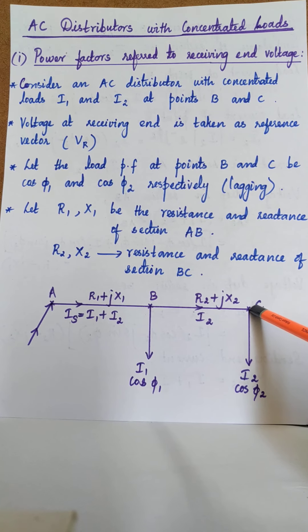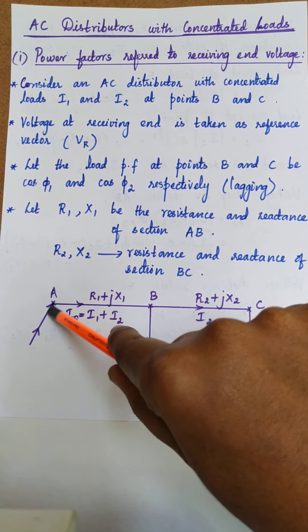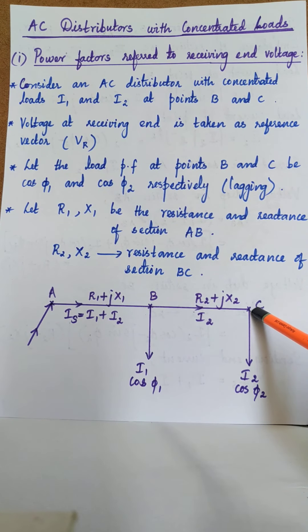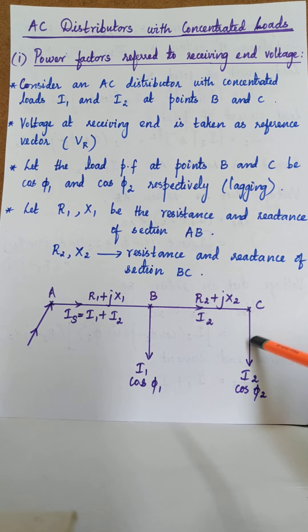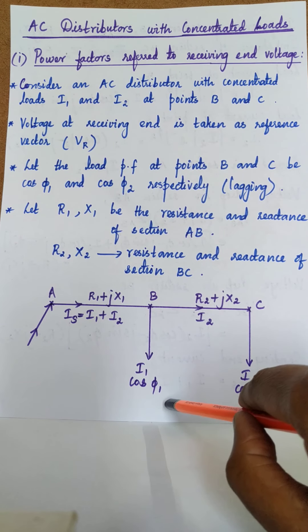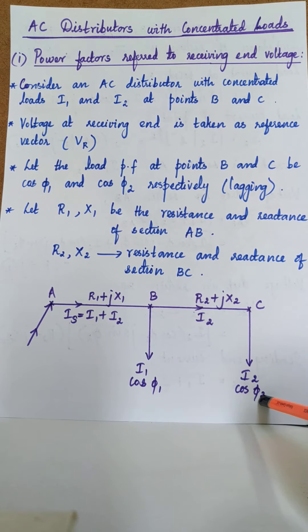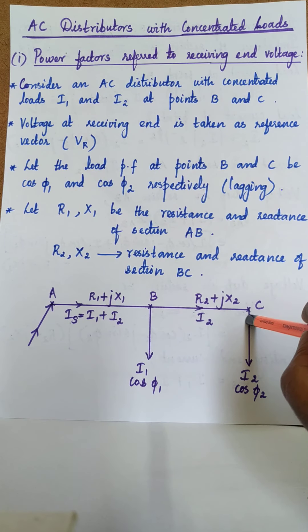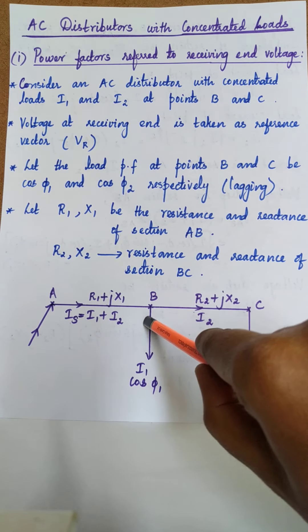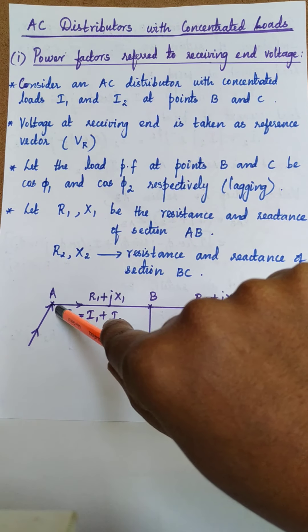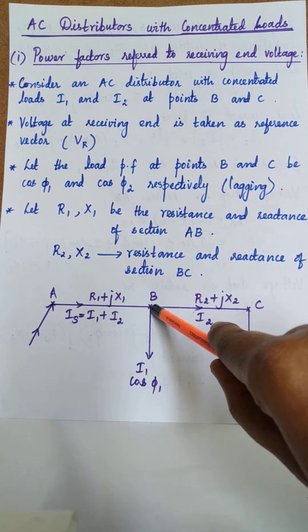The receiving end side is point C, and the sending end side is point A. The receiving end voltage at point C is Vr. Usually the loads will be lagging — RL loads. So we have considered cos phi 1 and cos phi 2 as lagging power factor. Since there are two concentrated loads I1 and I2 at B and C, we divide this distributor into two sections: section AB and section BC.